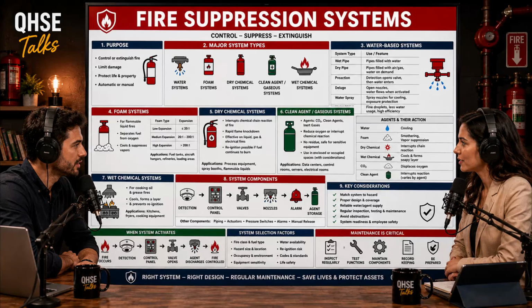I agree. Let's talk about the operational reality of taking a massive sprinkler system offline for maintenance. A facility manager can't just shut the main water valve off and go to lunch, right? Absolutely not. Disabling a fire protection system creates a severe vulnerability known as a system impairment. There are strict protocols. First, you must formally notify the local fire department and your corporate insurance carrier. Because if a fire happens, the fire department needs to know they are walking into an unprotected building.